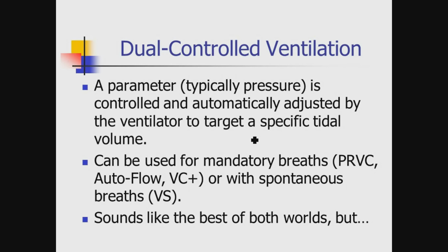And every breath it looks at the previous one and raises or lowers the pressure control level to target my tidal volume. So it was a way to accomplish volume ventilation with a fixed, quote-unquote, tidal volume, but still have variable flow rates that the patient can attain.